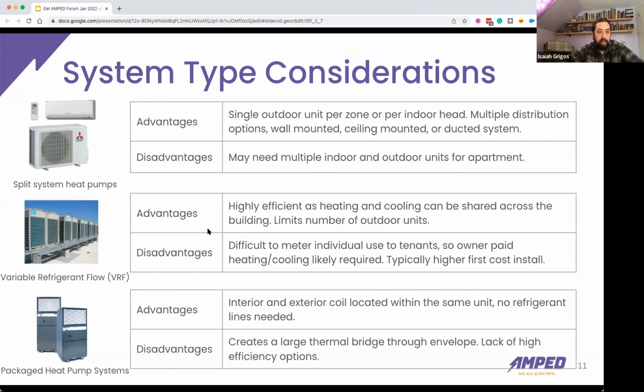They're also great because they can be a little bit more efficient than your standard split system heat pump because they can have heat recovery, where basically a part of the building is in cooling and another part is in heating. You move heat between apartments rather than trying to take it from the outside, which can increase the efficiency by like 10 to 15%.